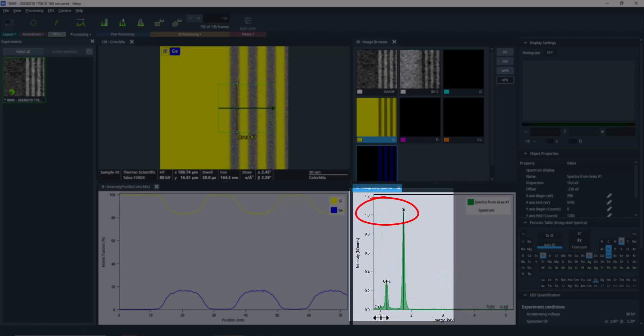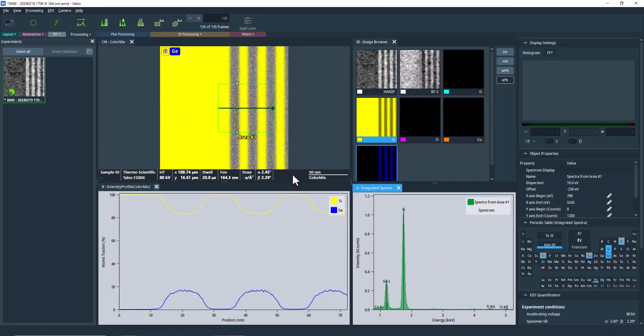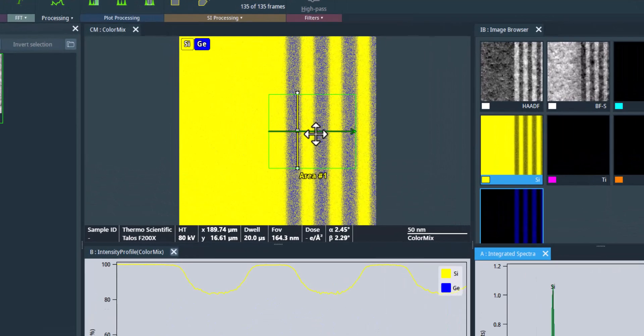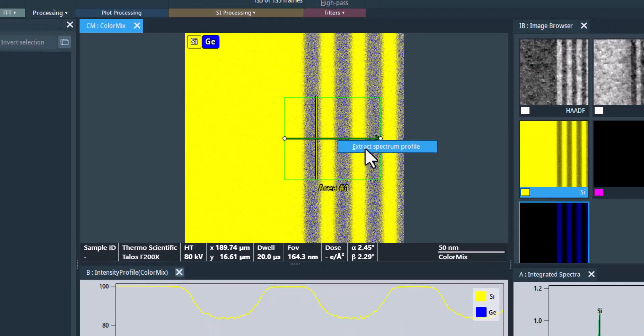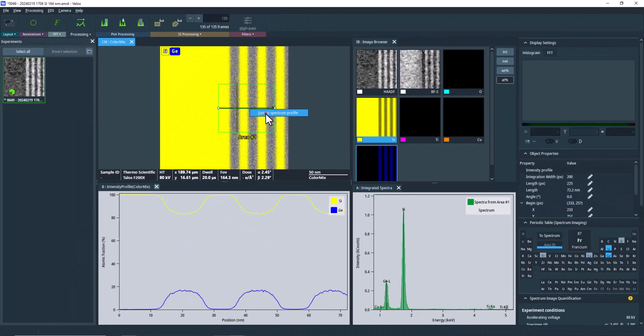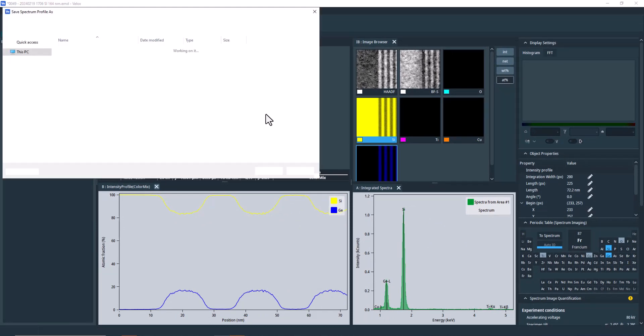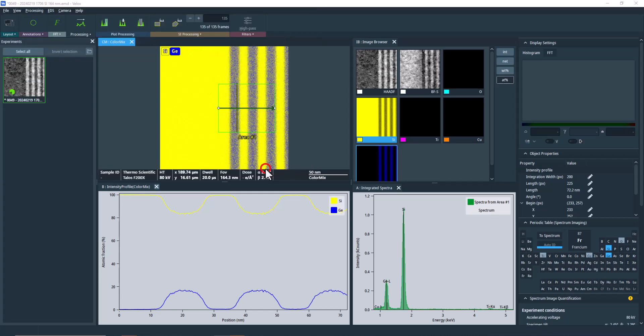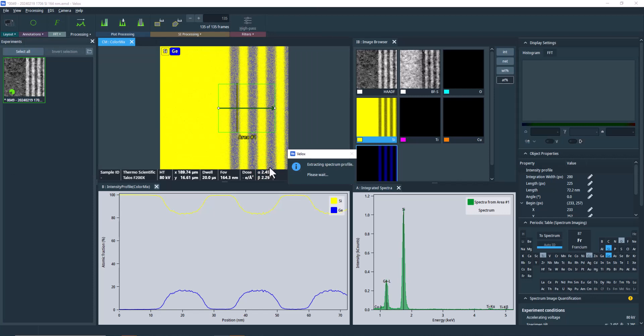And we can generate a spectrum profile to leverage the higher statistics along the width of the profile. To do this, right-click on the profile and from the context menu select Extract Spectrum Profile. Next, you'll need to specify where to save the profile. The profile will be generated into a separate EMD file. The new file will automatically be opened in a separate instance of Velox.